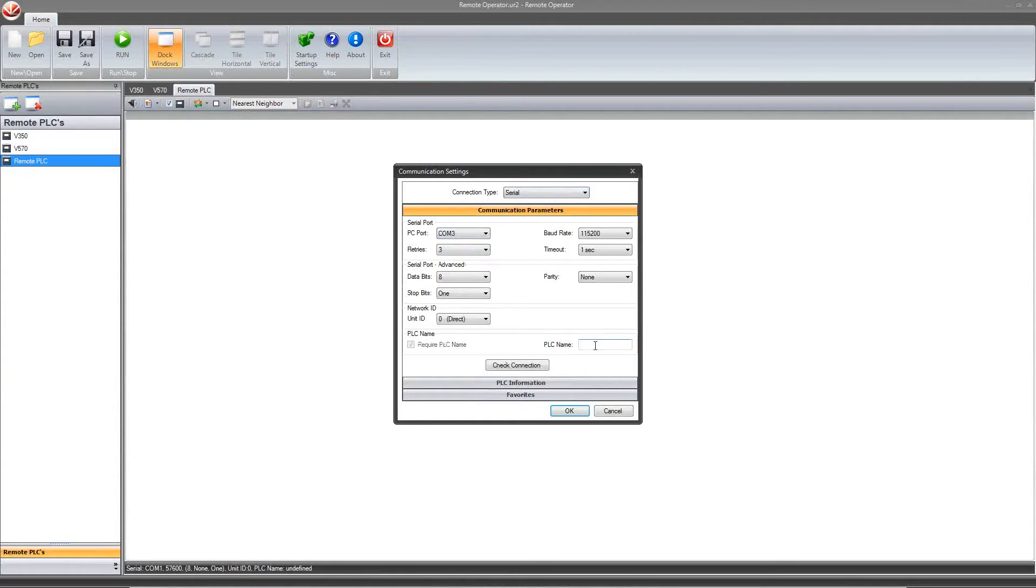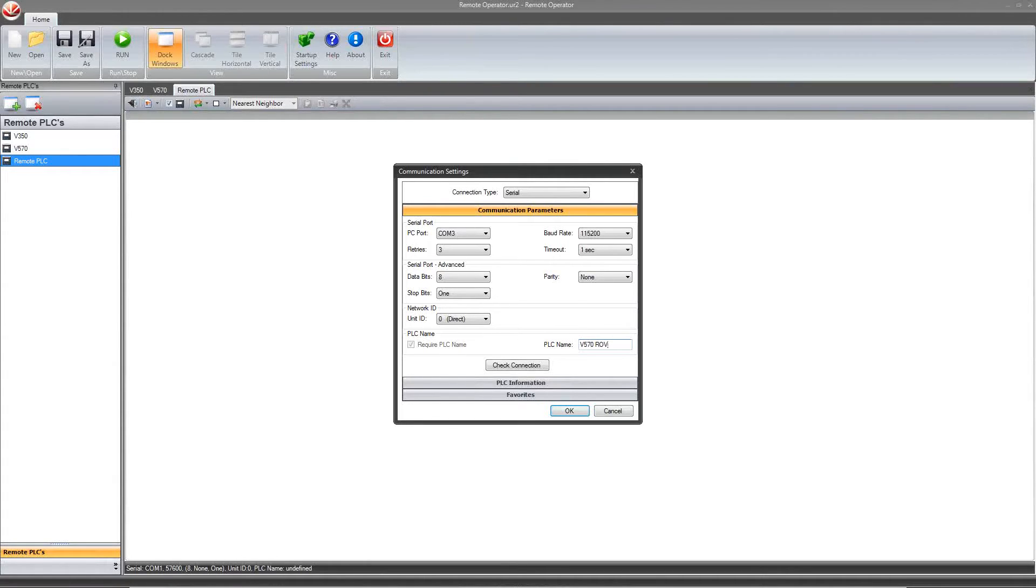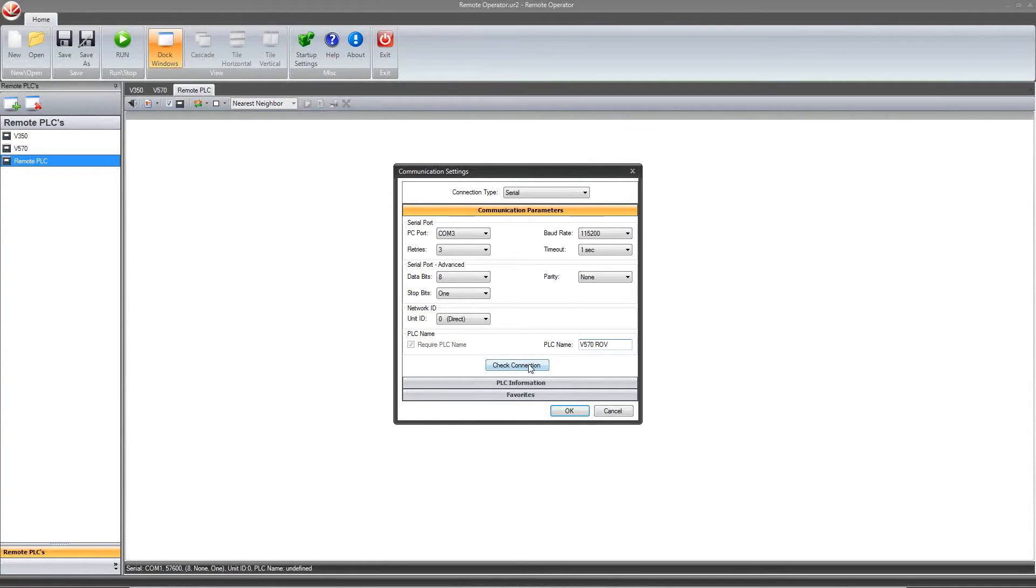I have defined the PLC name previously in the program as V570 ROV. This can be defined with a function block within VisiLogic, or if it is already defined, viewed from your controller via info mode within software information. Please note, it is not possible to connect to a controller if you do not have the PLC name. Once we have defined the communication parameters, click check to make sure we can make a proper connection with the controller.